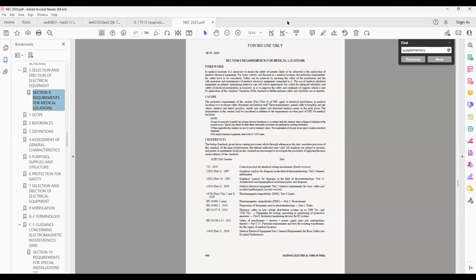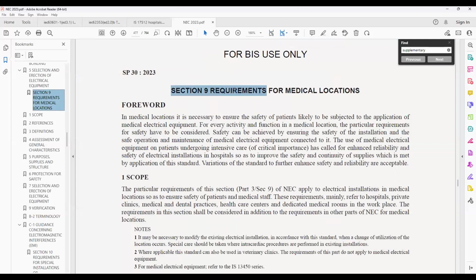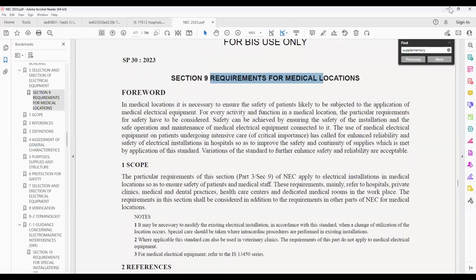Very easy. You can download the National Electrical Code of India 2023. You can go to the BIS website, create a username and password, search for National Electrical Code of India, and download it free of cost. It's a 750-page document. Now, part 1 of NEC is 100% applicable. You have to apply it 100%. Then you go to part 9. Part 3 section 9 explains the requirement for medical locations. So for medical locations, additional safety measures are required. Basically we are talking about a very critical installation which can catch fire, and this installation needs several safety measures and the attention of several engineers, or engineering practices basically.